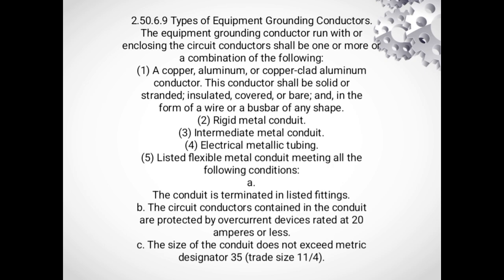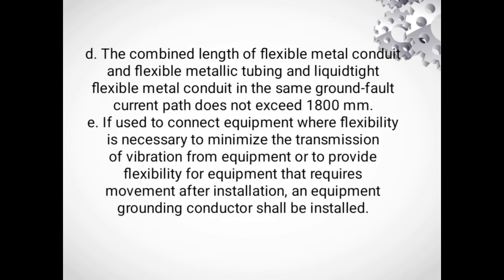5. Listed flexible metal conduit meeting all the following conditions. A. The conduit is terminated in listed fitting. B. The circuit conductors contained in the conduit are protected by overcurrent devices rated at 20 amperes or less. C. The size of the conduit does not exceed metric designator 35, trade size 1 1/4. D. Combined length of flexible metal conduit and flexible metallic tubing and liquidtight flexible metal conduit in the same ground fault current path does not exceed 1,800 mm. E. If used to connect equipment where flexibility is necessary to minimize the transmission of vibration from equipment or to provide flexibility for equipment that requires movement after installation, an equipment grounding conductor shall be installed.